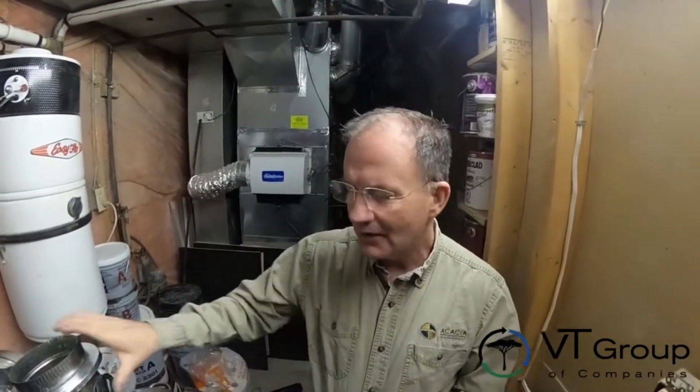So if you've got an older home that doesn't have one, I would recommend, when you're doing a furnace upgrade or some maintenance or even draft proofing on your house, think about getting a Hoyme, that's H-O-Y-M-E, make-up air or fresh air intake damper. That's what these look like. I would actually recommend mounting it closer to the outside. This one here would be closer to the inside, and this would only open when the furnace fan is actually heating. So that meets code requirements and gives you the fresh air when the fan is running, but when you're just circulating the air, the damper is closed.